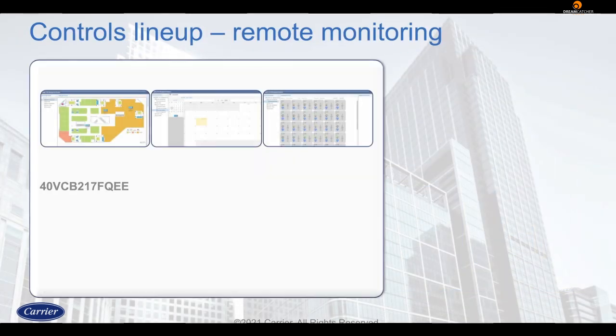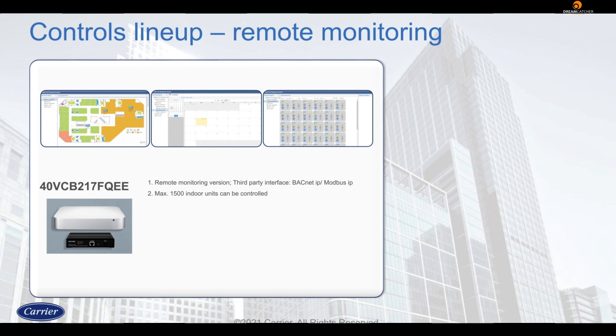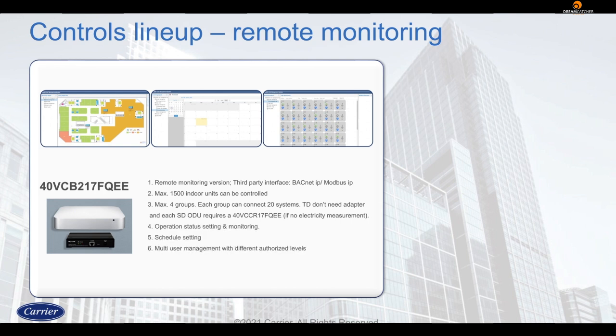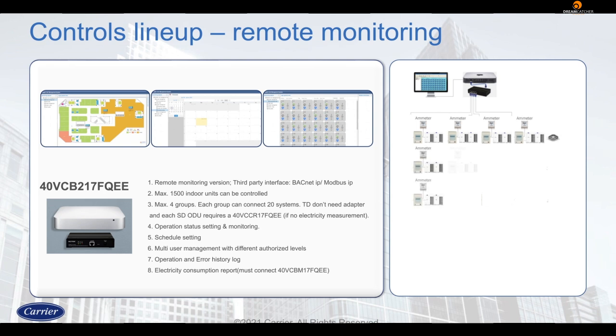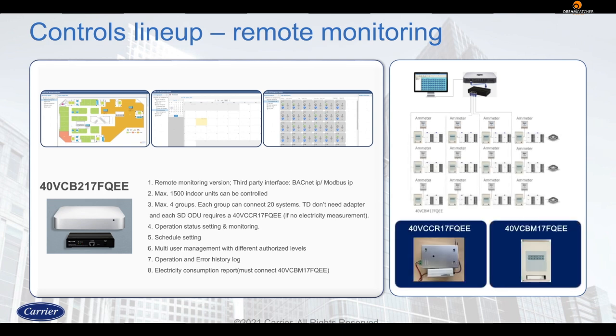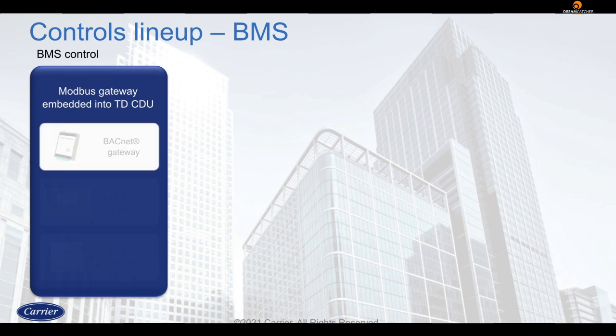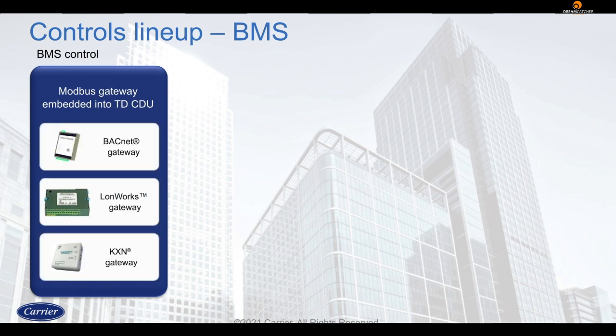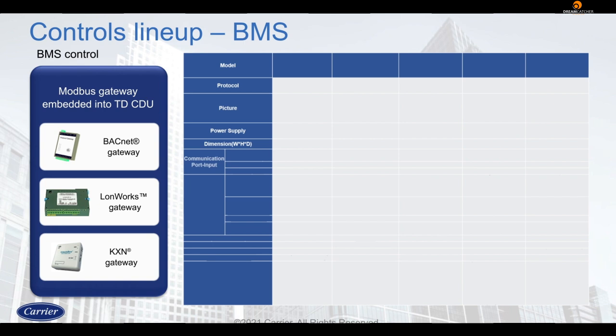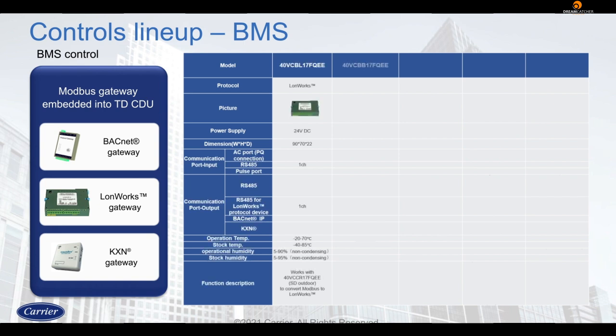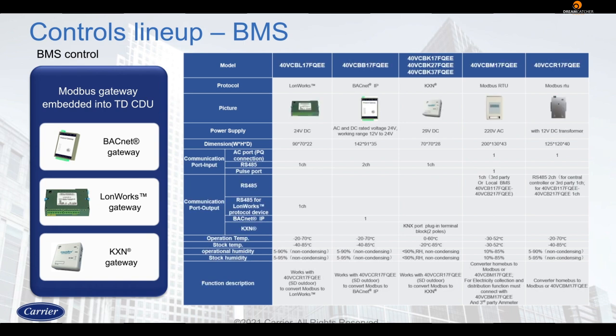Remote monitoring enables you to connect up to 1,500 indoor units and offers support for 4 groups of 20 systems. You can even perform operation status settings and monitoring, schedule settings, set multi-user management, check operation and error logs, and view the electricity consumption report by combining with the Electricity Adapter Unit. The BMS control can be set up through a Modbus gateway embedded in the top discharge outdoor unit. It can connect with the BACnet gateway, LonWorks gateway, and KNX gateway.